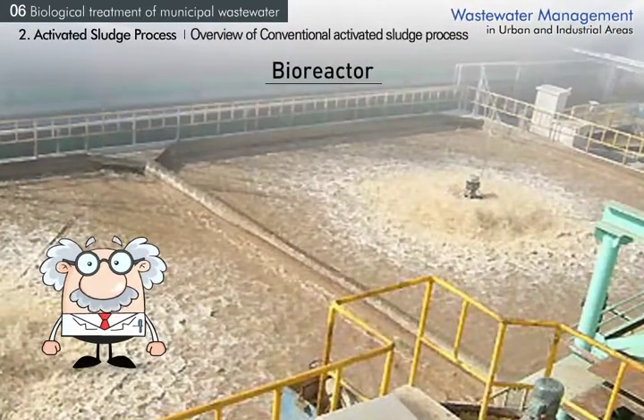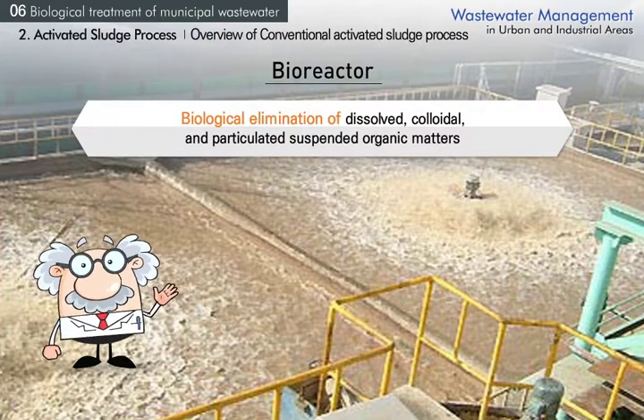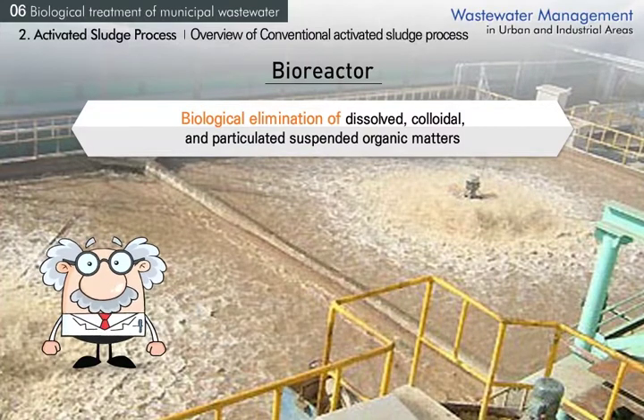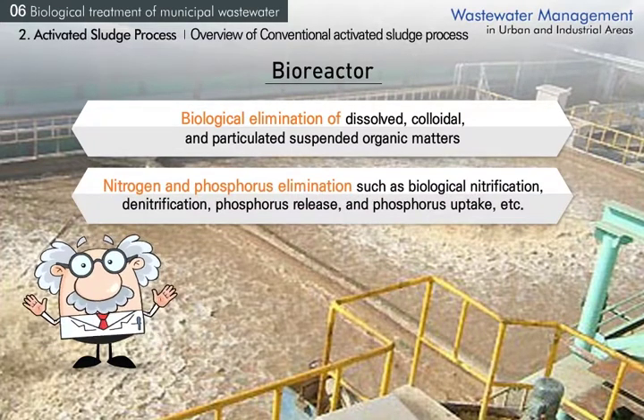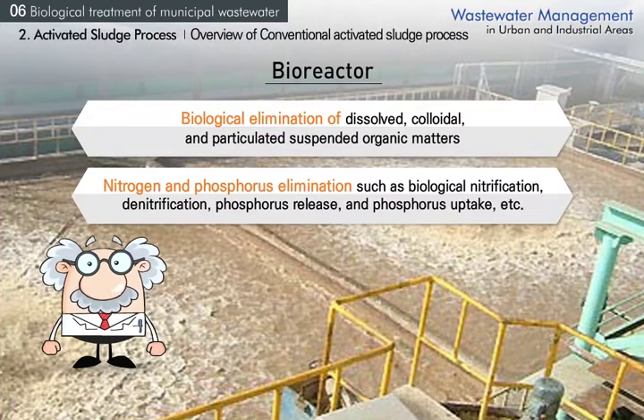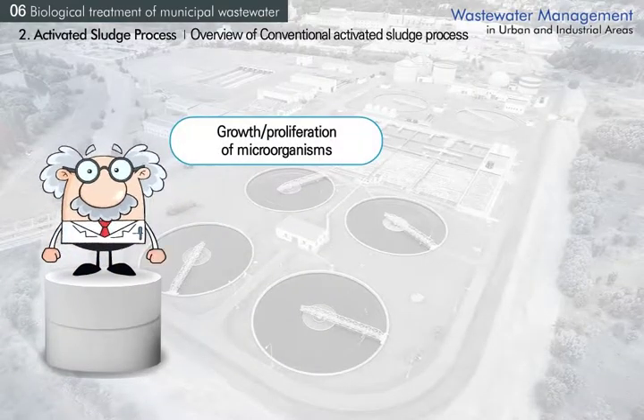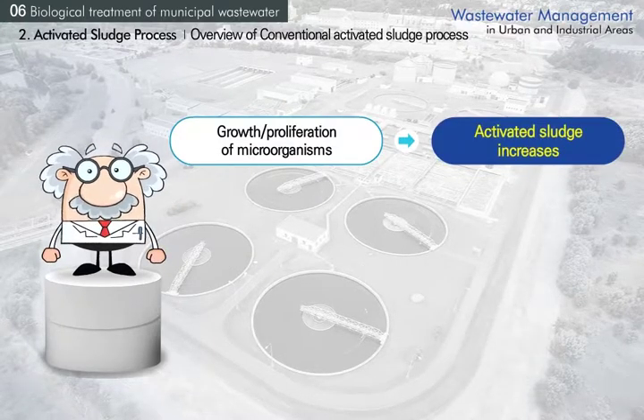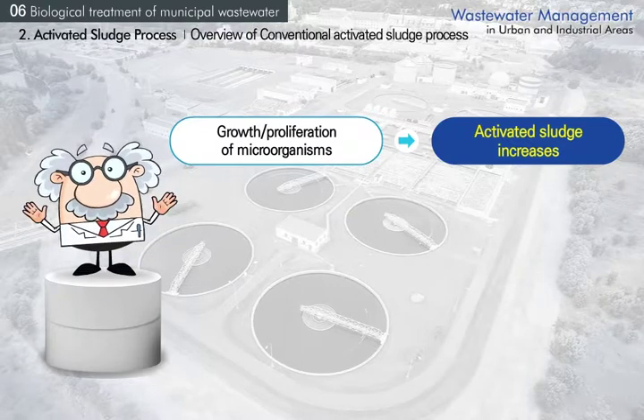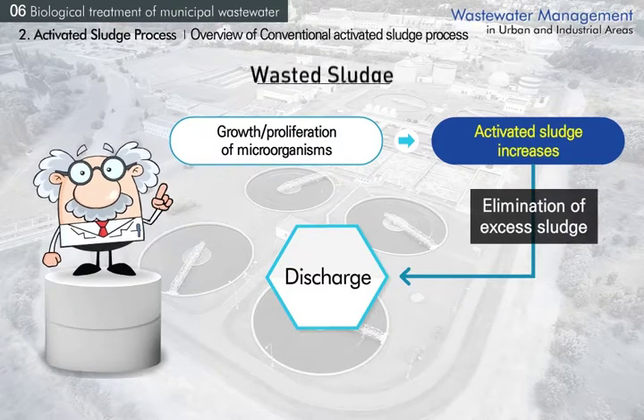In the bioreactor of the activated sludge process, dissolved, colloidal, and particulate suspended organic matters are biologically eliminated. Depending on operating conditions and reaction processes, nitrogen and phosphorus can also be eliminated through nitrification, denitrification, phosphorus release and uptake. While wastewater pollutants are treated, microorganisms grow and proliferate, gradually increasing the amount of activated sludge. To maintain a certain concentration in the bioreactor, excess sludge is eliminated and discharged outside the system as wasted sludge.